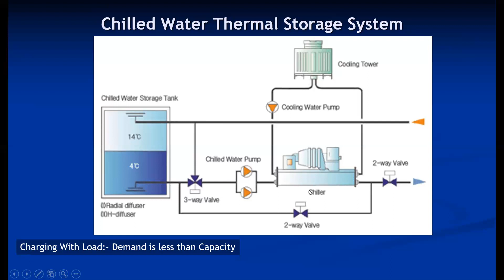The second mode is when the demand is almost negligible. Suppose the demand is only 10 kilowatt, but the chiller is continuously producing 100 kilowatt. Only the chilled water required for 10 kilowatt goes through the supply line, and the remaining chilled water is stored in the storage tank. So in this case, charging without load or with negligible load happens. So this is the second condition: charging without any load, or with negligible load.